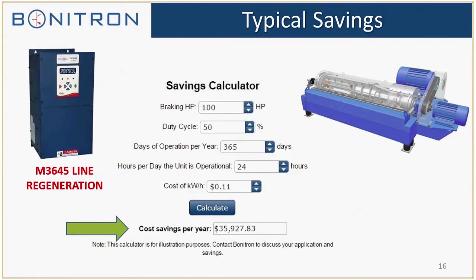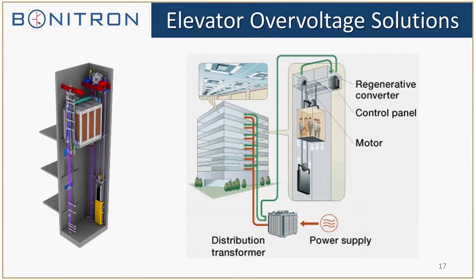Typical savings here: at a 100 horsepower motor at 50% duty cycle, operating 365 days at 24 hours a day at 11 cents per kWh, your cost savings per year will come to $35,927.83. Those are very large savings per centrifuge. If you have someone with five or six of those centrifuges in the facility, that adds up quickly.